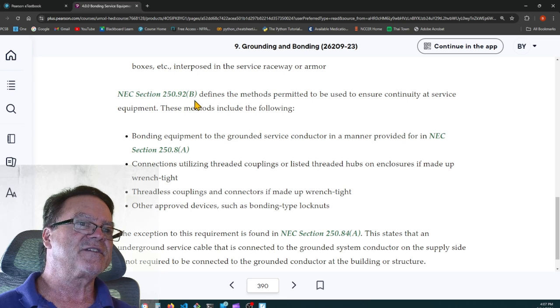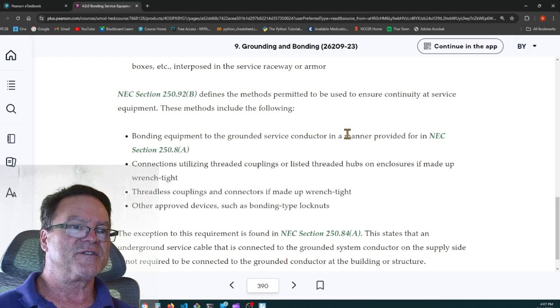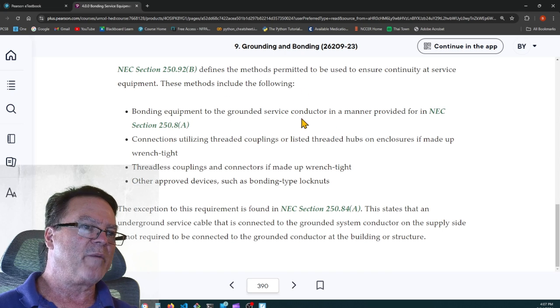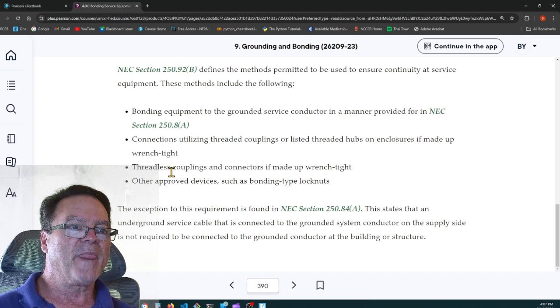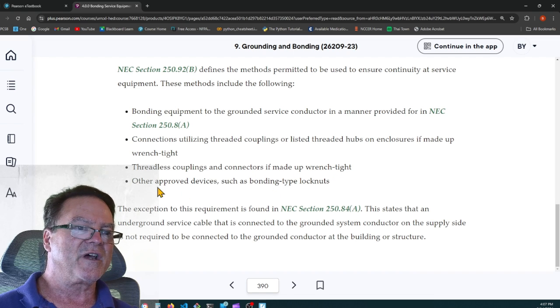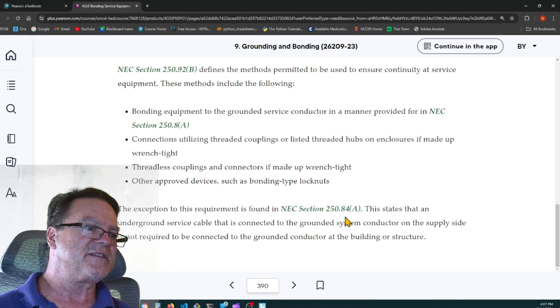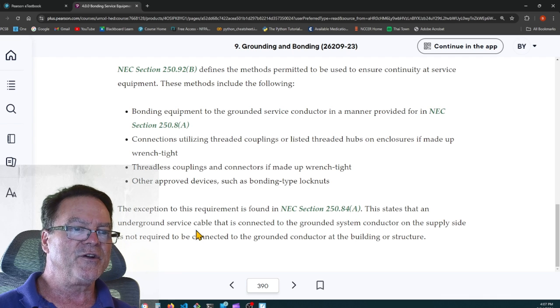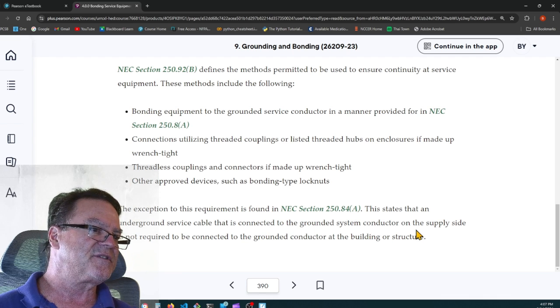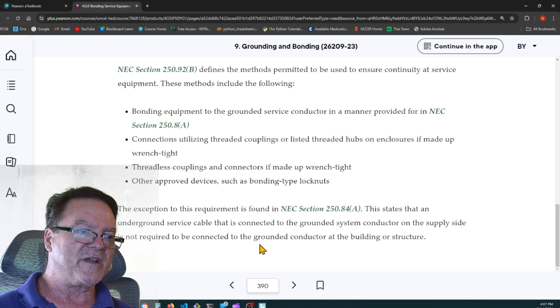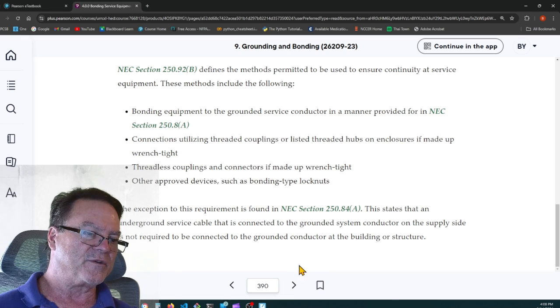Oh, I'm sorry, here it says that NEC section 250.92B defines the methods permitted to be used to ensure continuity at service equipment, and they include bonding equipment to the grounded service conductor in a manner provided for in section 250.8A. Connections utilizing threaded couplings or listed threaded hubs on enclosures if made up wrench tight. Threadless couplings and connectors if made up wrench tight. Other approved devices such as bonding type lock nuts. The exception to this requirement is found in NEC section 250.84A. It states that an underground service cable that is connected to the grounded system conductor on the supply side is not required to be connected to the grounded conductor at the building or structure.